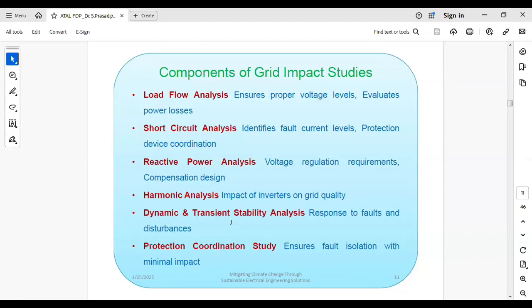And then the last one is protection coordination study. As I already said, you have to go for the relay coordination study whenever you are installing a PV plant. What should be the size of the circuit breaker? What should be the relay? How to coordinate the relay so that whenever a fault happens in the system, the minimum part of the system is disconnected instead of the major part of the network. So proper relay coordination has to be done for smooth and reliable operation of the PV plant.